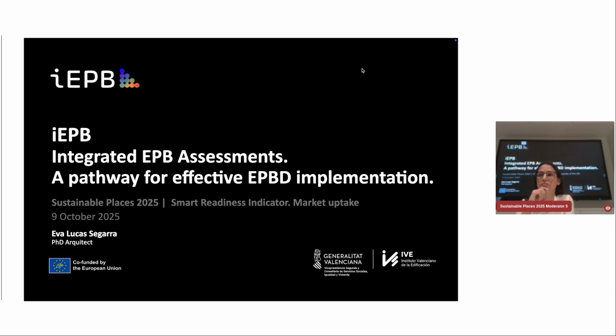because I asked them for justification of the functionality level selection, and that shows their real expertise when they try to explain why they selected this functionality level. I ask for the description, at least a basic description, of the installation and how the service is managed at building level. Then when you check the justification, the comments, you see when somebody knows about it and when not. So it's very, very clear.